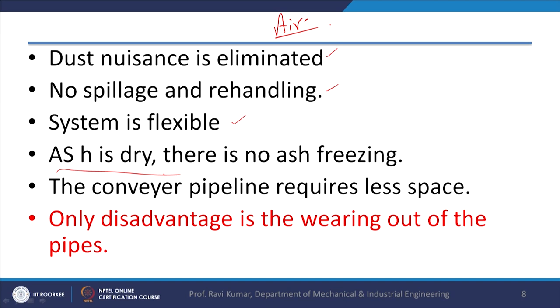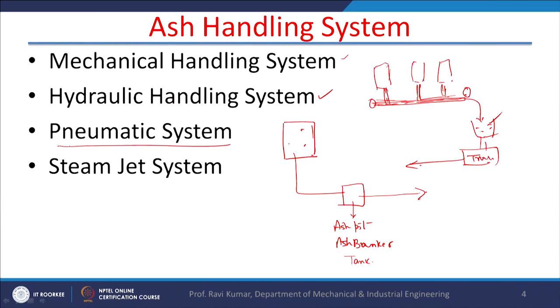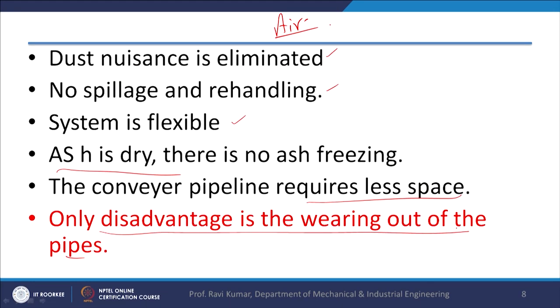In the pneumatic system, ash is dry and only piping is required; ash comes into the pipe and is removed by forced air. The main disadvantage is wearing out of the pipe, because ash particles act as abrasive material. The ash particles move at very high velocity, causing abrasive wear, and therefore frequent maintenance is required in such systems.